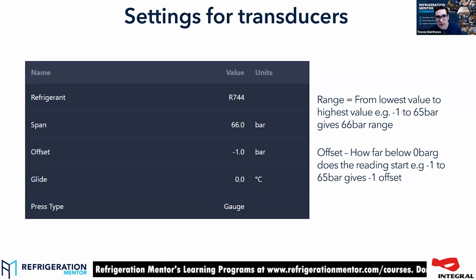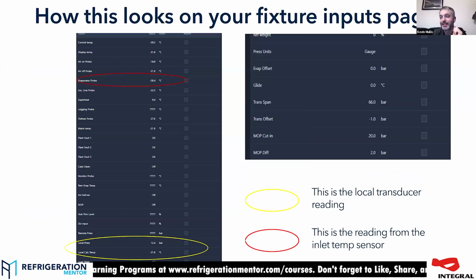And then exactly what you said there. You've got a 1,000 psi transducer when you're only running in a 20 psi range. You can't expect it. You've only got 16 milliamps to cover that whole range. You're asking it to be very accurate.